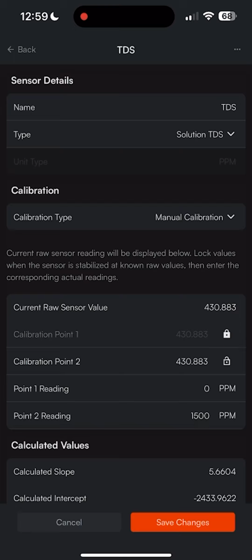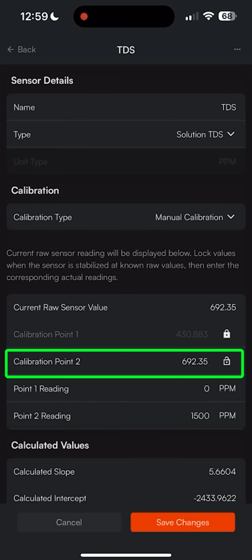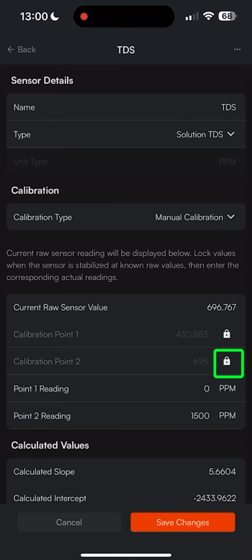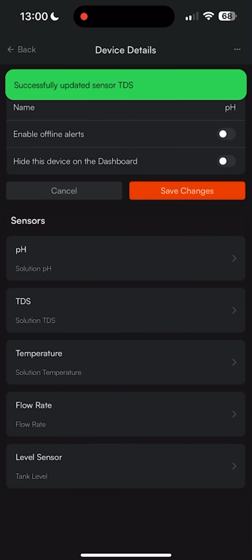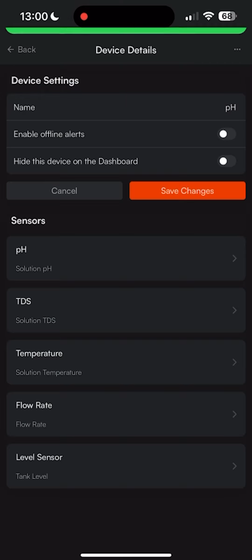Next, you'll place the TDS probe in your conductivity standard, wait for the readings to change, and once those readings have equalized, tap the lock icon to lock in that sensor reading. With the sensor reading equalized, all that's left is to lock in that calibration point and then save changes, as these readings are used to make a calibration equation that you can see at the bottom of the page.